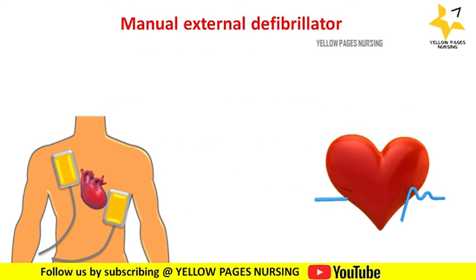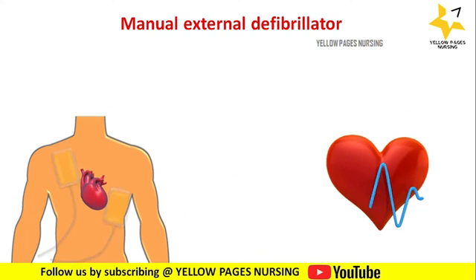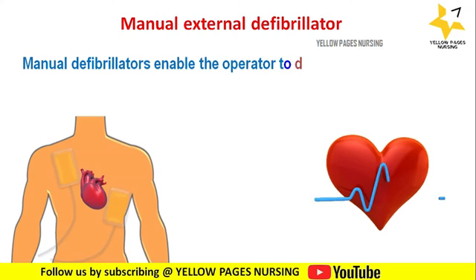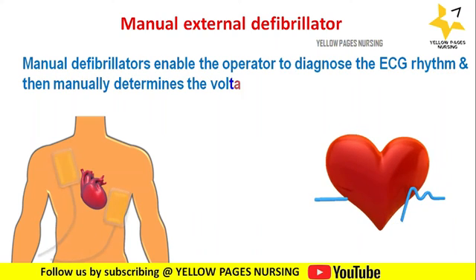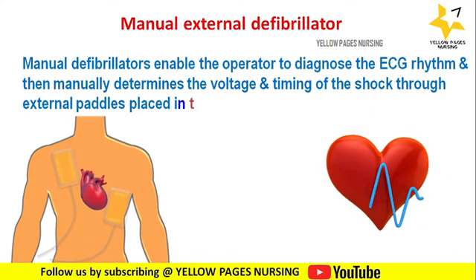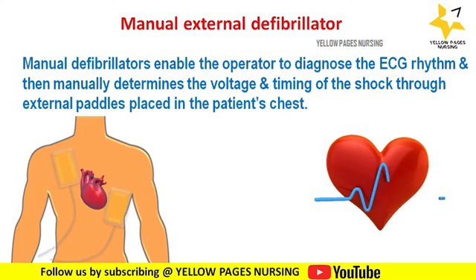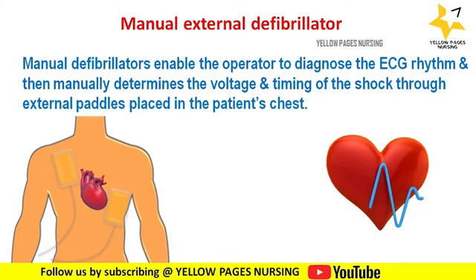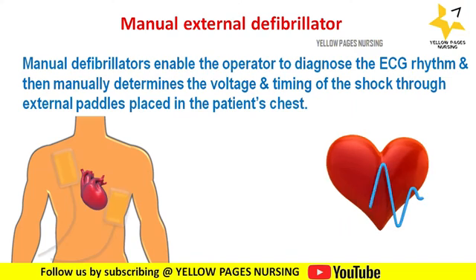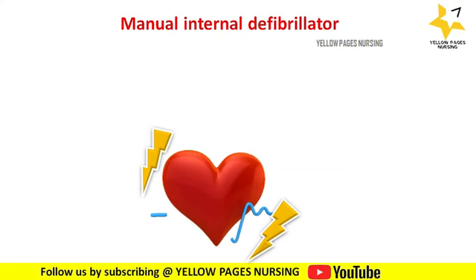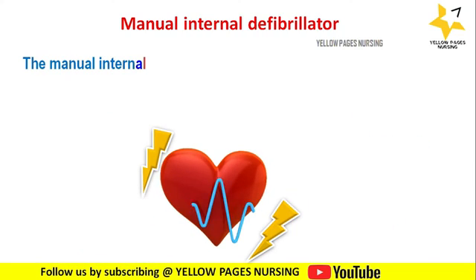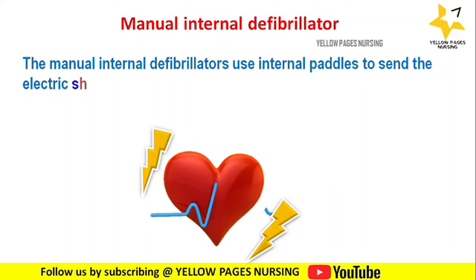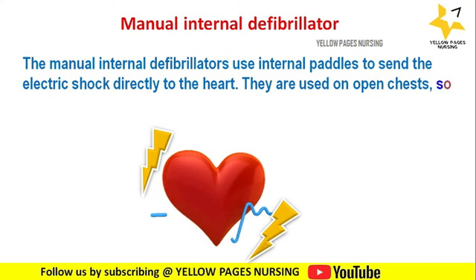Manual external defibrillators enable the operator to diagnose the ECG rhythm and then manually determine the voltage and timing of the shock through external paddles placed on the patient's chest. This can be handled only by trained personnel.